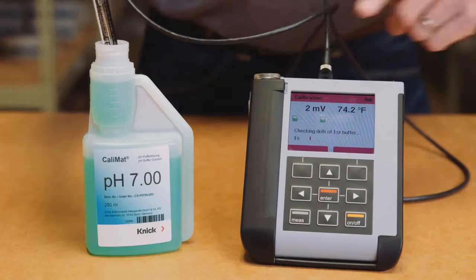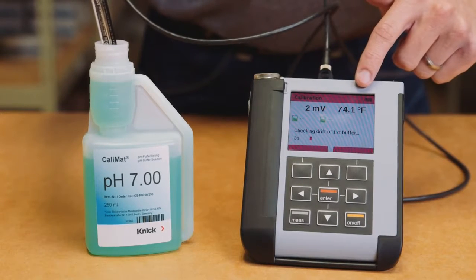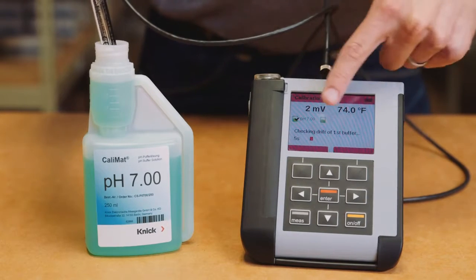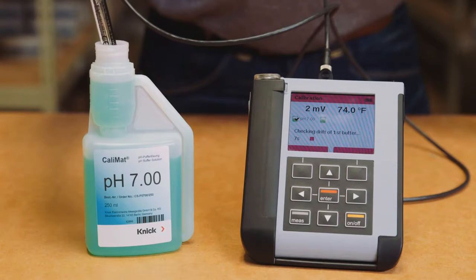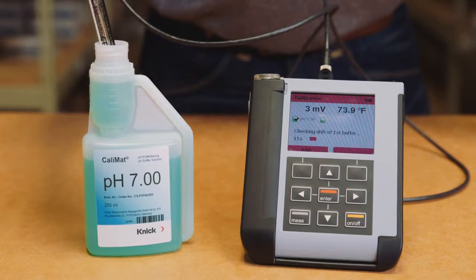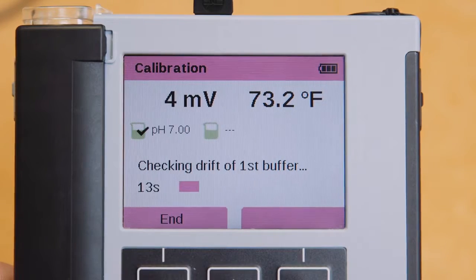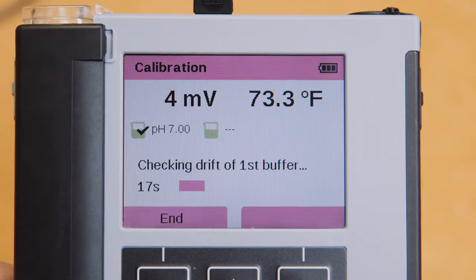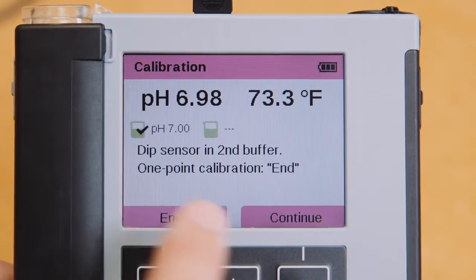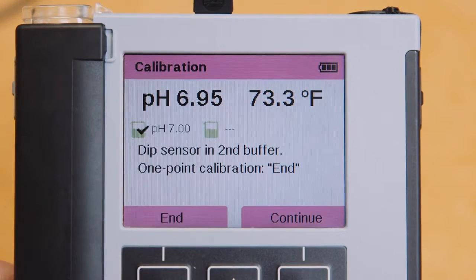After pressing the Continue button, the Portavo checks the drift of the first buffer solution. As you can see, it displays the millivolt output generated by the sensor in the first buffer solution, as well as the measured temperature value. The Portavo automatically indicates a buffer value of 7.00 based on the millivolt output of the sensor. Once it is finished with the first buffer solution, the Portavo then prompts us to go ahead and dip the sensor in the second buffer.